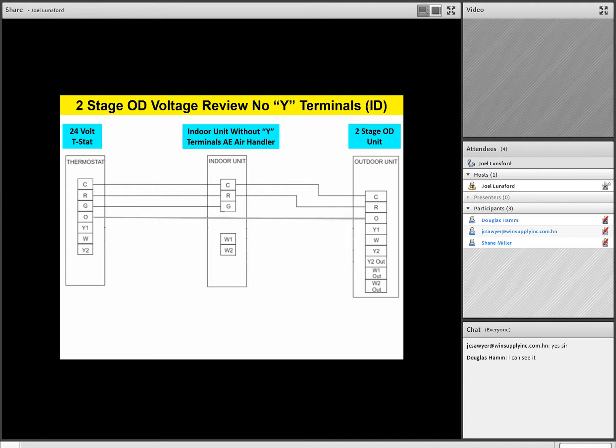So in our previous examples, we took C and we took it all the way through, C to C to C. R terminal goes R, R, R, just like we did before. Same way with O terminal. The O terminal goes all the way through from the thermostat straight to the outdoor unit, because there is no O terminal on the AE air handler, so that just goes straight through. But then let's talk about that G. So the G terminal from the thermostat goes to G on the indoor AE air handler as our example. It has no Y terminals at all. So the G terminal goes to G on the indoor unit.